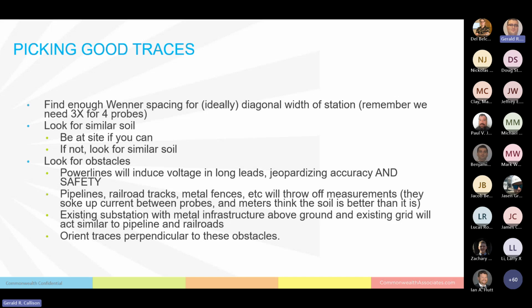Another thing that does the same is an existing substation with metal infrastructure, like an existing ground grid, which will pick up the current. Just last week, I had to reject some soil measurements because they were taken within about 10 feet, parallel to an existing substation with an existing ground grid. Sure enough, those soil numbers looked a lot better than I was expecting based on the boring reports. So never do that—never run parallel to existing metal infrastructure like a railroad, pipeline, or existing ground grid.